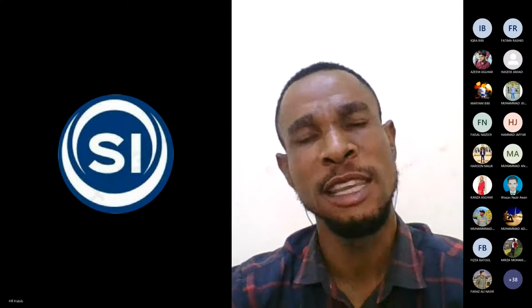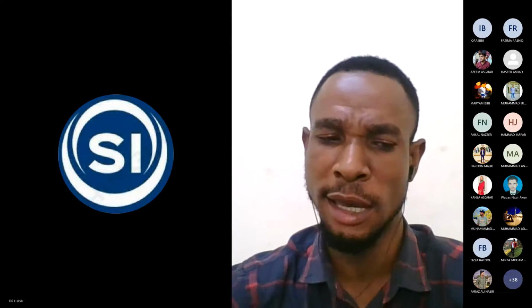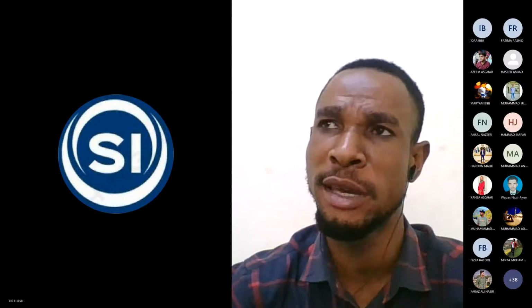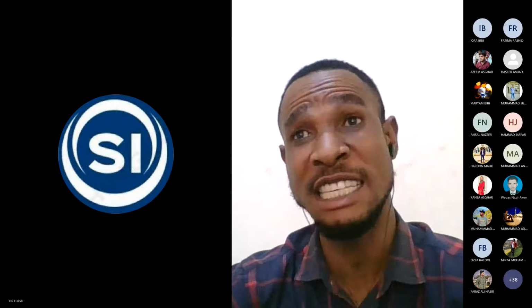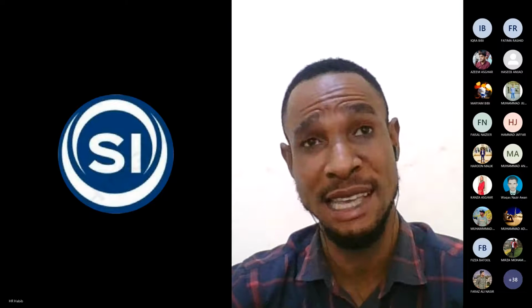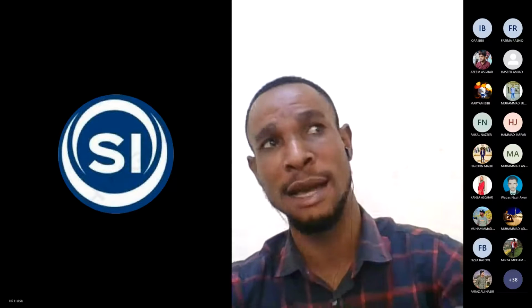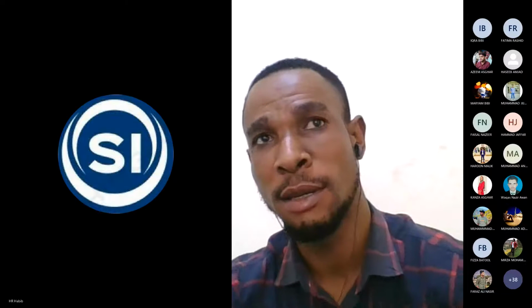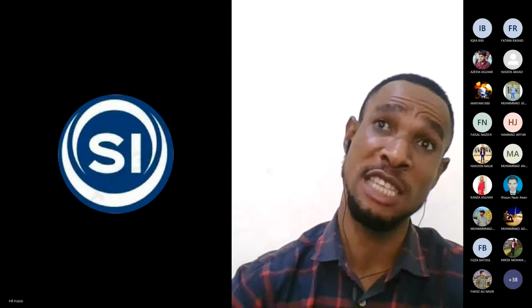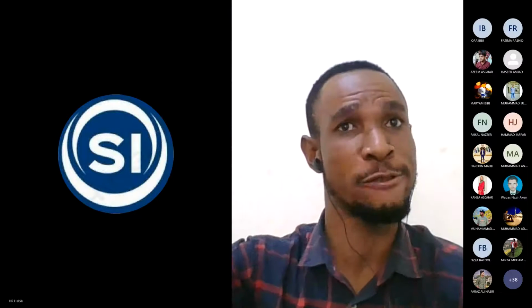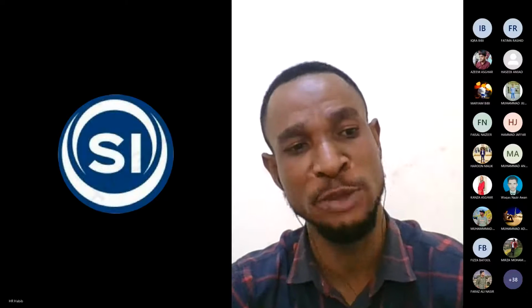Another panel I find inside the control room is called the MV panel, the medium voltage panel. The purpose of the medium voltage panel is, for example, if you have a customer, because the whole essence of establishing a gas power plant is either you want to use it in a factory or you want to sell the power to a customer. For example, if the factory is located at a distance from where the gas power plant is installed, you will need to use the medium voltage panel.